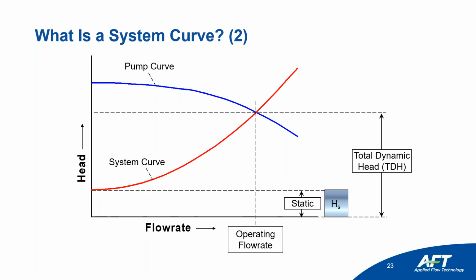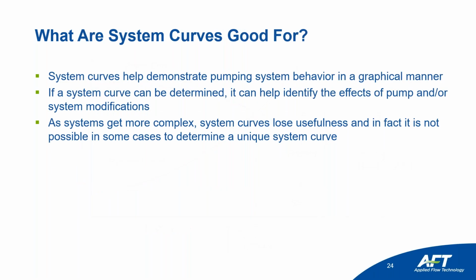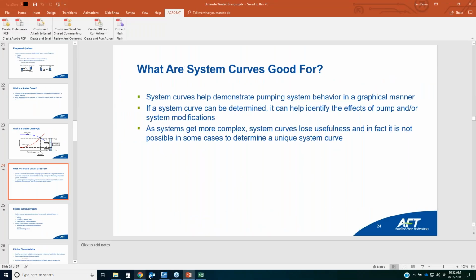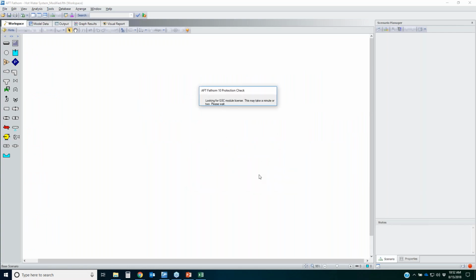Your static head, again, that is your liquid surface elevation differences. And then you've got your frictional head component. So your frictional head plus your static head is your total dynamic head. Total dynamic head is what your pump curve is reading off. What are system curves good for? They will help you demonstrate your pumping system behavior in a graphical manner. If you can determine a pump and system curve, it can help you identify effects or impacts of modifying the system. So let me give you an example now that my model is open here.